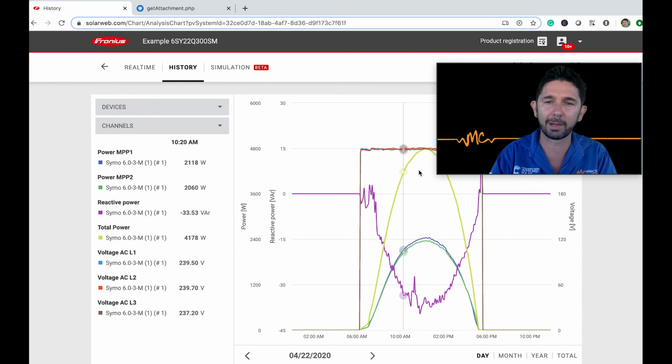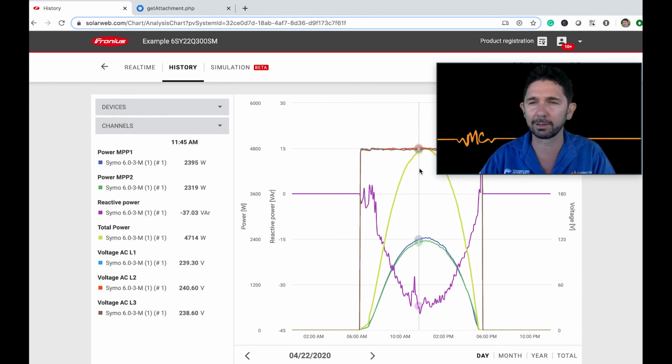But one thing that we have picked up with this is we can see the voltage of each tracker. We've got the details of how many panels we put in a string. And let's say there's 10 panels in a string, then your voltage should be sitting, let's say, around 300 volts. But if that voltage drops back to 270 volts, we've found quite often that there is a Tigo optimizer failed. And we've gone into every single job that we've had Tigo optimizers and checked that. And we've found a few have failed over time.